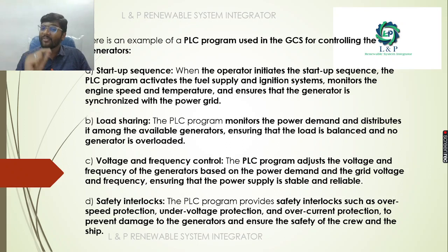Next is the voltage and the frequency control. It adjusts the voltage and the frequency of the generator based on the power demand and the grid voltage and the frequency, ensuring that the power supply is stable and reliable. Next is the safety interlock, such as overspeed protection, under voltage protection, over current protection, which prevents the generator from damage and ensures the safety of the crew and the ship.